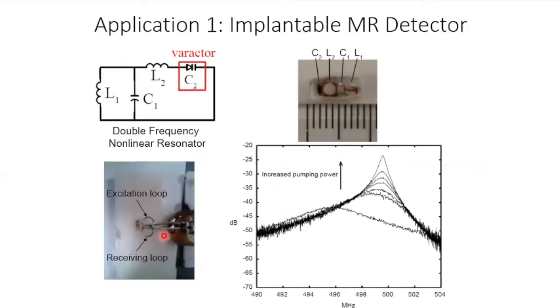And then we use a pair of loop antennas connected to a network analyzer to analyze its power response, this frequency response curve. As we can see in this plot, when the sensor is in its passive mode, its center frequency is about 496 megahertz. But as we crank up the pumping power, the sensor center frequency gradually shifts to 500 megahertz with the increased height of its power transmission curve. So that's to say that we can wirelessly tune the off-resonance sensor to operate at 500 megahertz, which is the normal frequency of a 11.7 Tesla scanner.